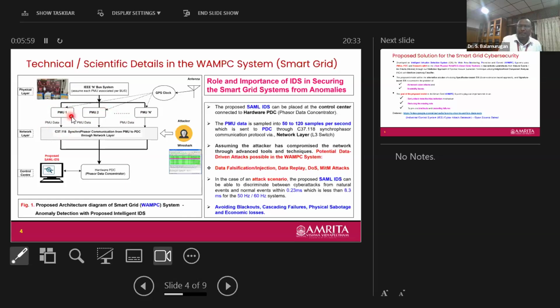As per the PMU, it can capture 120 samples per second with a time-synchronized GPS clock. These samples are pushed into the phasor data concentrator, where you have the state level dispatch center, the super PDC, and the regional dispatch center, connected through an L3 switch, a layer 3 switch, using the C37.118 synchrophasor communication protocol from PMU to PDC.